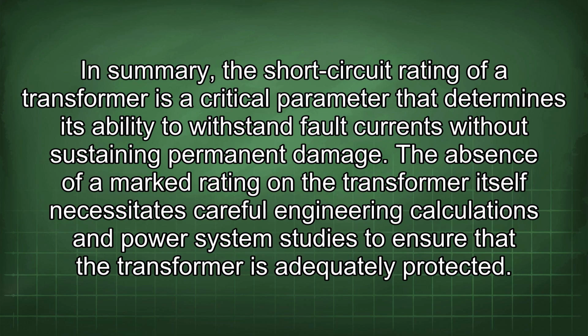In summary, the short circuit rating of a transformer is a critical parameter that determines its ability to withstand fault currents without sustaining permanent damage. The absence of a marked rating on the transformer itself necessitates careful engineering calculations and power system studies to ensure that the transformer is adequately protected.